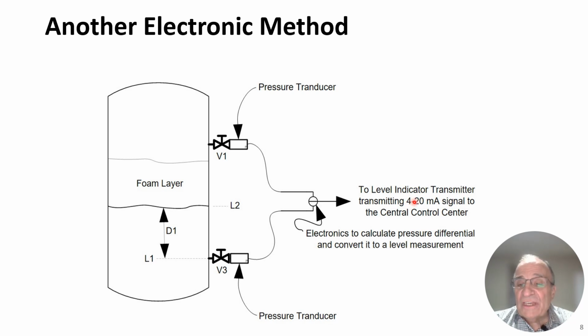12 would be 50% level because the difference between 4 and 20 is 16. So 8, which is half of 16, plus 4 gives you 12 milliamp, which would be 50% scale, and then 20 milliamp would be full scale. And that's just another method of using electronics to tell you what the level is. But it does not get rid of the problem of foam layer, especially if that foam layer is higher than the top tap that's shown here.